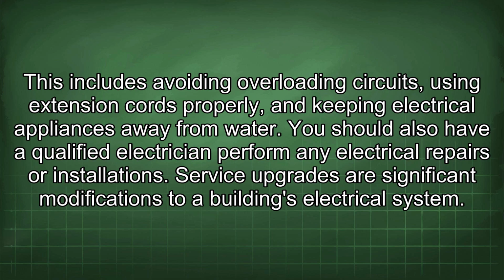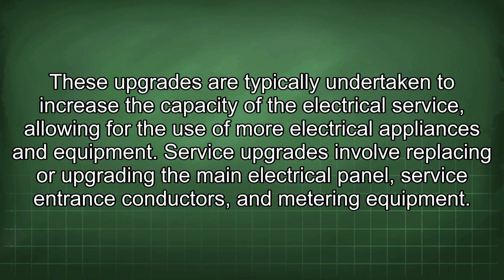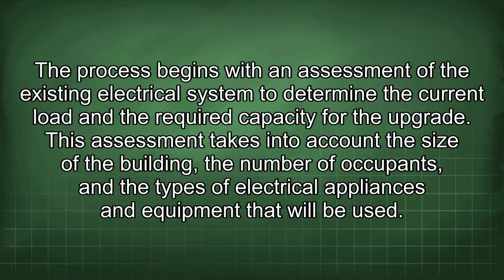Service upgrades are significant modifications to a building's electrical system. These upgrades are typically undertaken to increase the capacity of the electrical service, allowing for the use of more electrical appliances and equipment. Service upgrades involve replacing or upgrading the main electrical panel, service entrance conductors, and metering equipment. The process begins with an assessment of the existing electrical system to determine the current load and the required capacity for the upgrade. This assessment takes into account the size of the building, the number of occupants, and the types of electrical appliances and equipment that will be used.